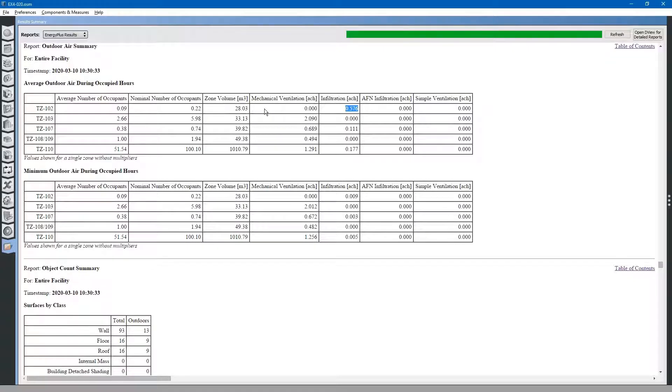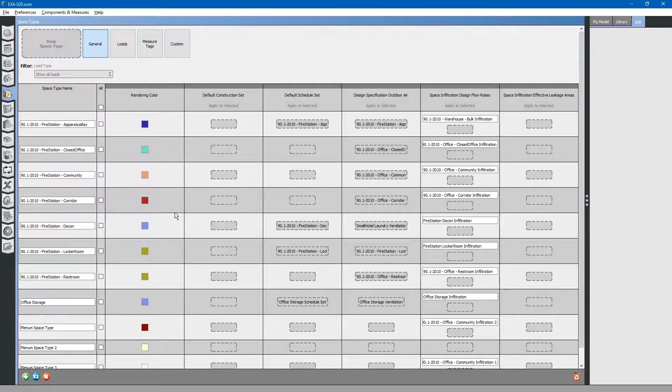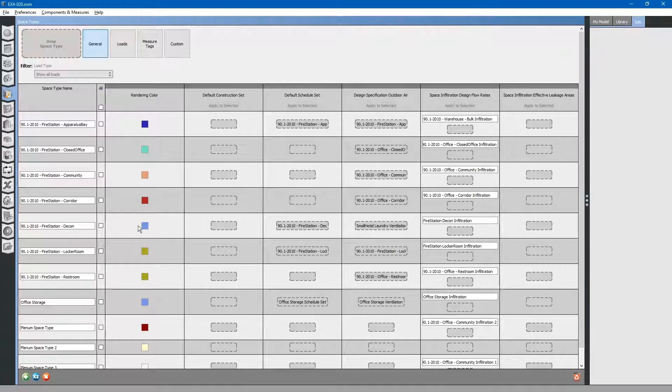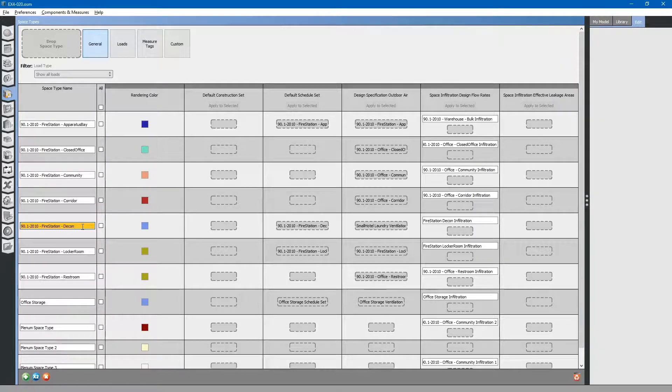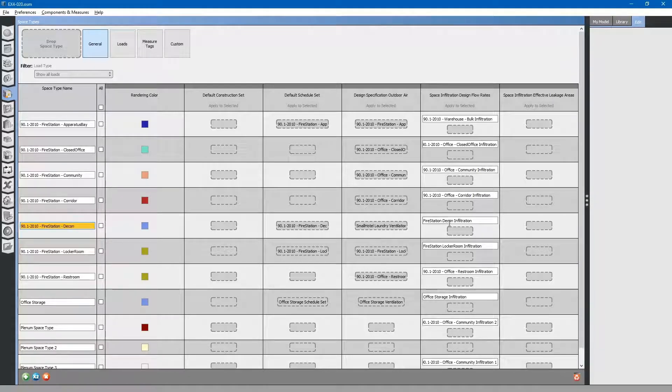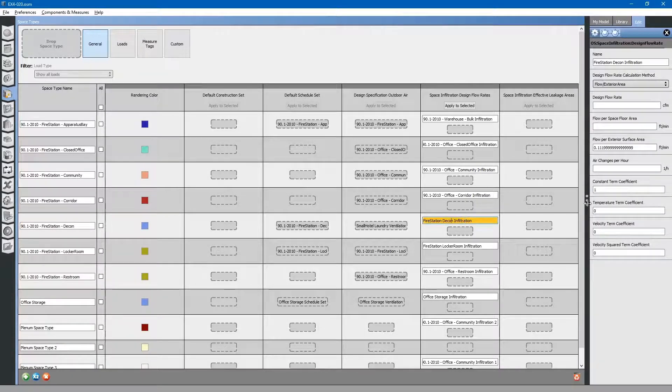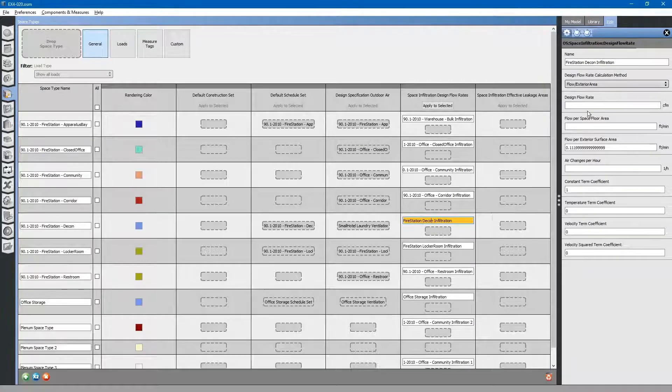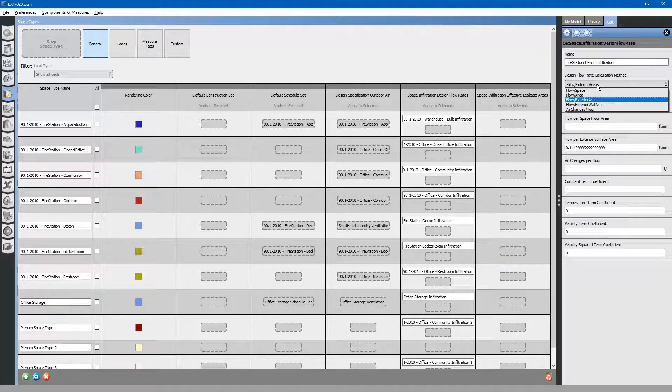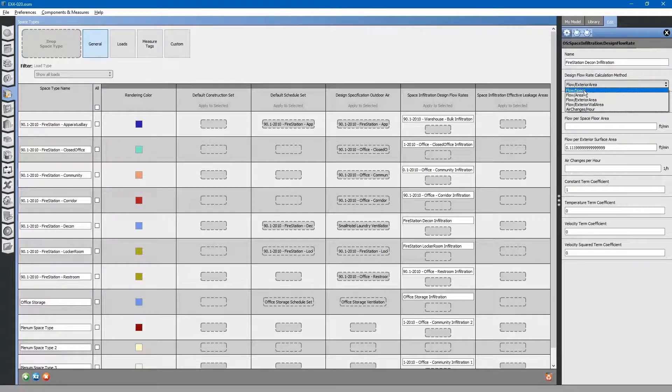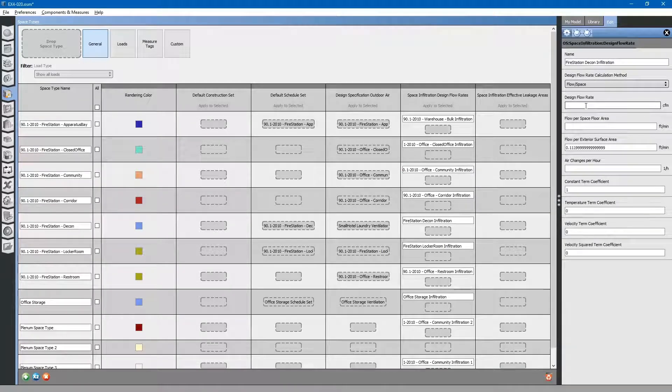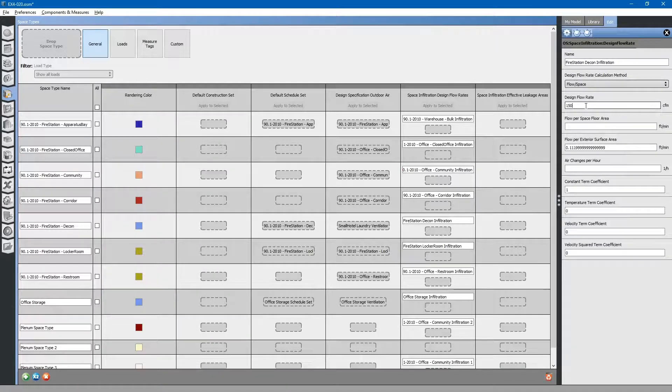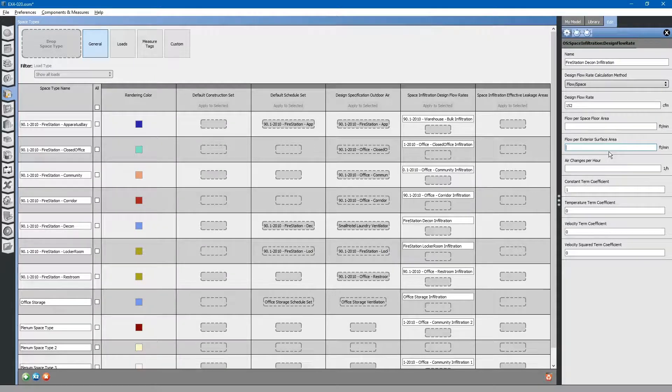Let's go back to the space types tab. In our laundry room decontamination room space type, we're going to have to edit this infiltration flow rate. We will change the design flow rate calculation method to flow per space. This will be the same value as what that exhaust fan is exhausting. We are adding 152 CFM. We will delete this flow per surface area.